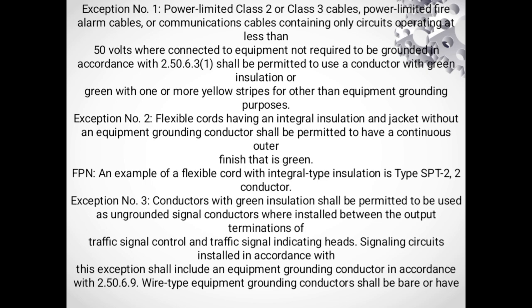Exception number 3, conductors with green insulation shall be permitted to be used as ungrounded signal conductors where installed between the output termination of traffic signal controllers and traffic signal indicating heads. Signaling circuits installed in accordance with this exception shall include an equipment grounding conductor in accordance with 2.50.6.9.